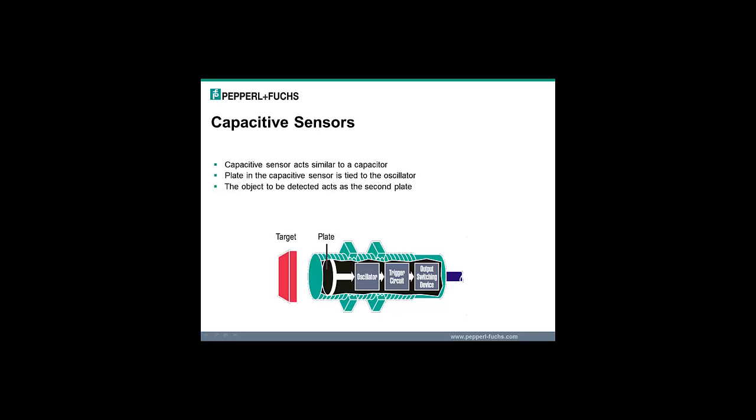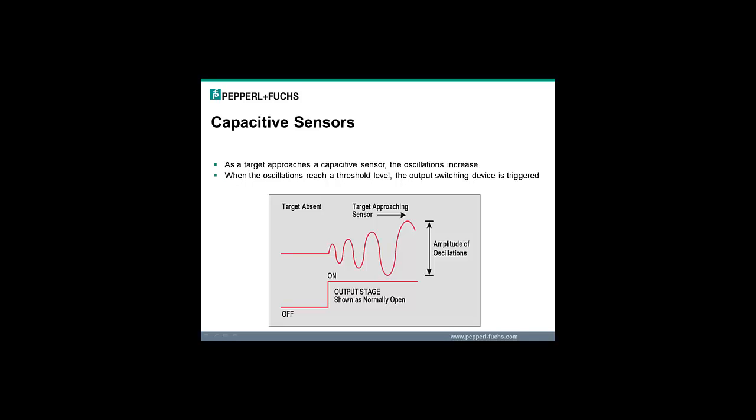The basic concept of a capacitive sensor is that it acts similar to a capacitor which has two plates. One plate inside the sensor is tied to the oscillator. The second plate is the target material. The sensor's rated distance is based on the test target, which is a grounded copper plate. As the target approaches the capacitive sensor, the internal oscillator begins and will increase in amplitude depending upon the target distance. When the internal oscillation reaches a defined threshold level, the output switching device is triggered and you will get an output from the sensor.